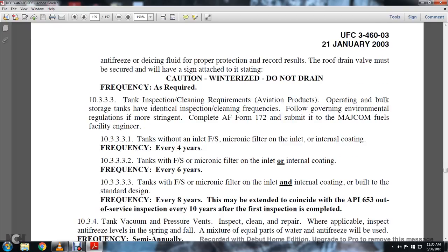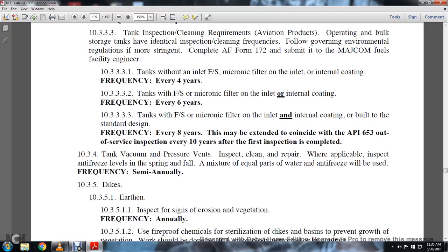10.3.3 Tanks. Filter separator or micronic filter on the inlet and internal coating both to the standard design. The frequency is every 8 years. This may extend to coincide with the API 653 out-of-service inspection every 10 years after the first inspection is completed.